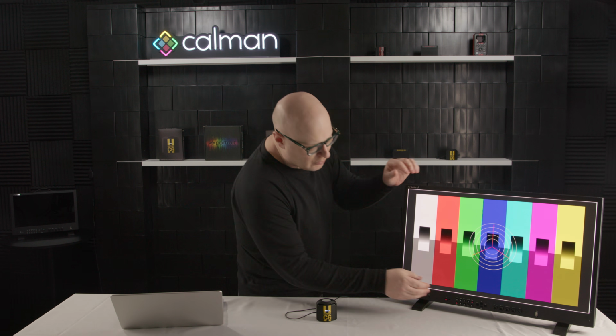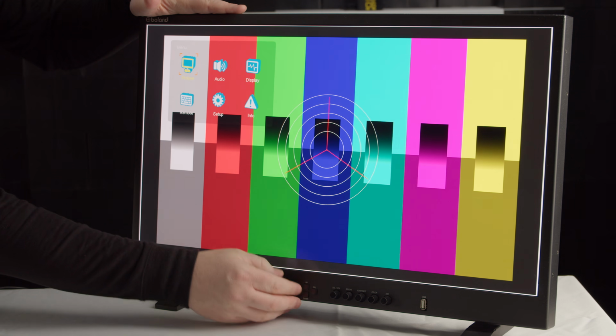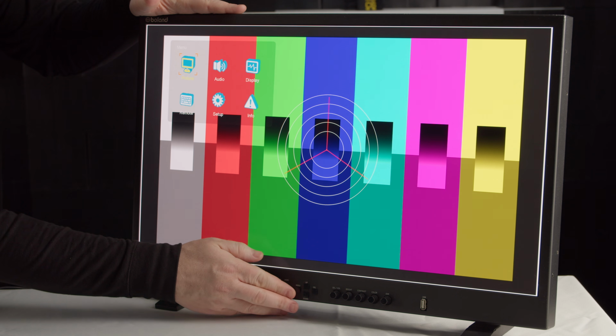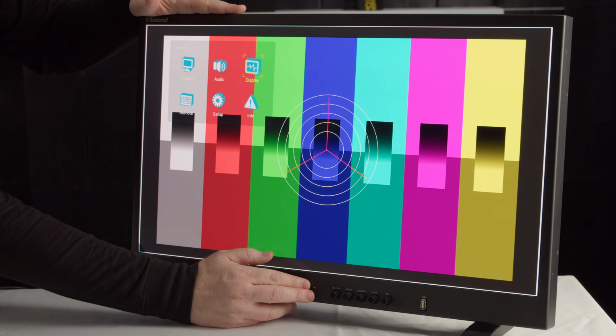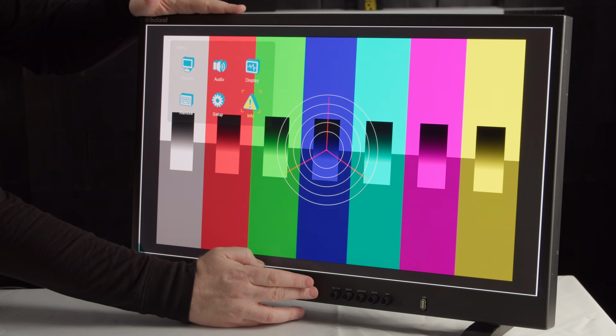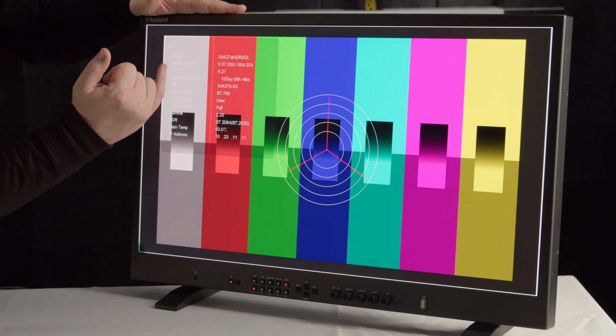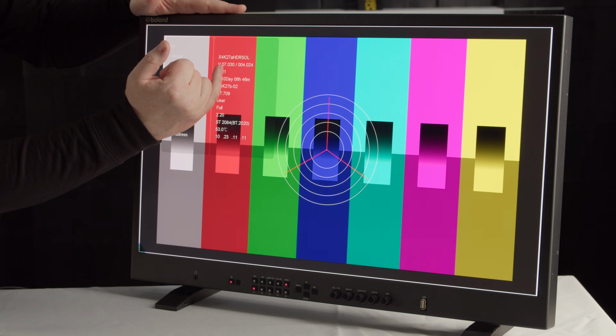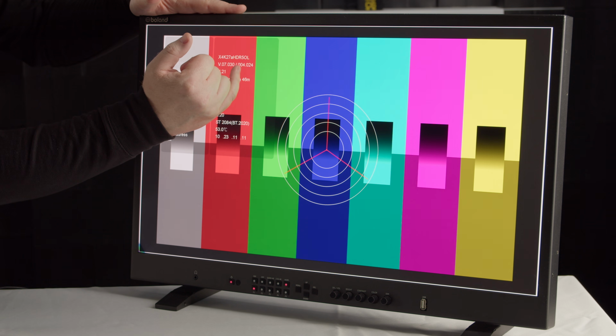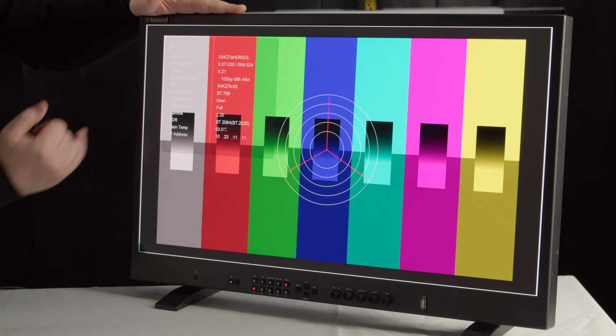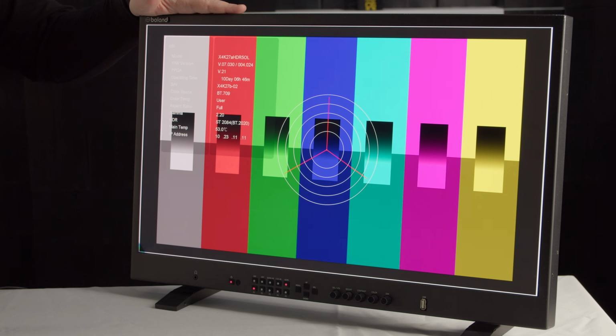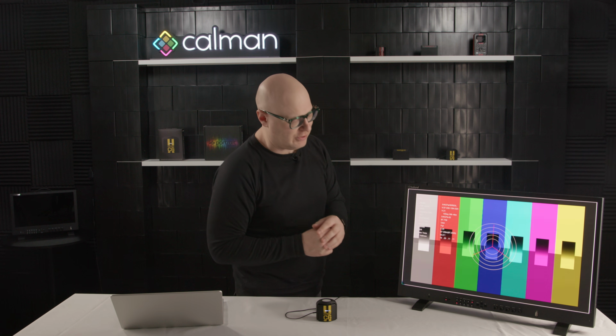Step 1: make sure you're running the correct firmware. Calman integration has been done with the latest firmware from Boland. I'll press the menu button, press the up arrow until I come to Info, and press Select. You'll notice my firmware version is 07.030.004.024 with version 21 on the FPGA. You'll want at least this version on your Boland monitor to use Calman's calibration features.